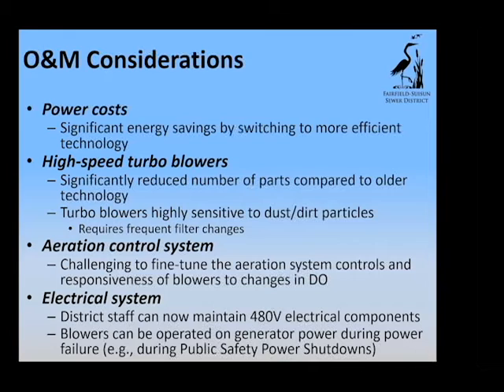Jordan mentioned the aeration control system. It was a little bit of a challenge when we were bringing these turbo blowers online. The way we had to sequence it, we had to bring part of our activated sludge process up on the new system while still maintaining the old system, then tune that new system, switch them, and then tune the old system. So it was a little tricky.